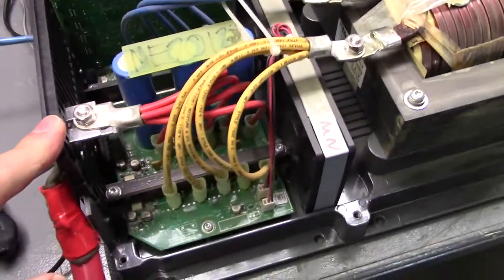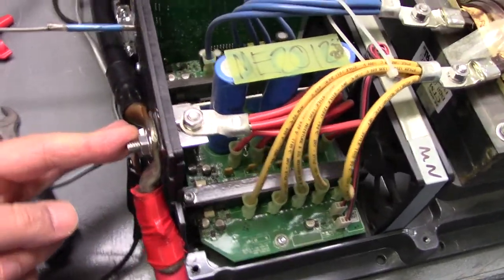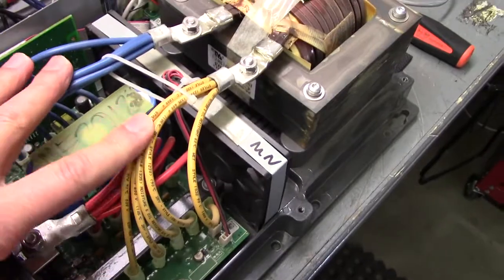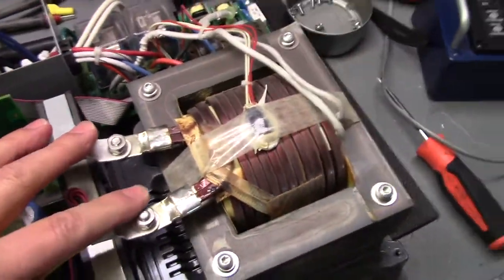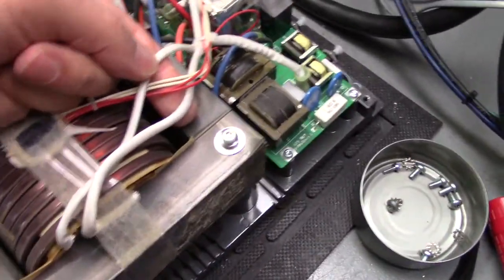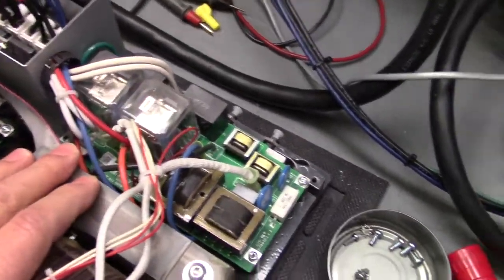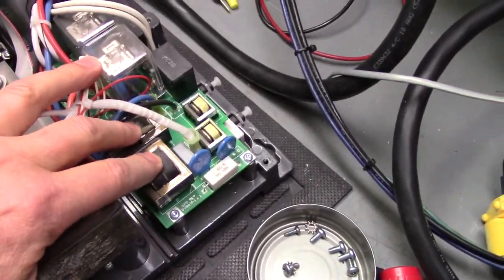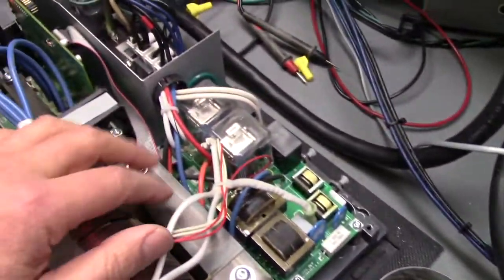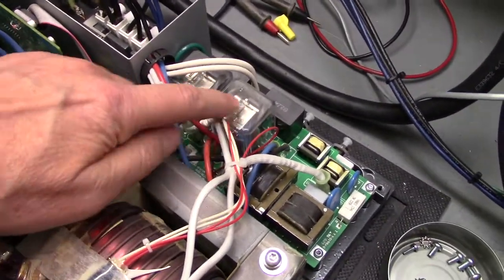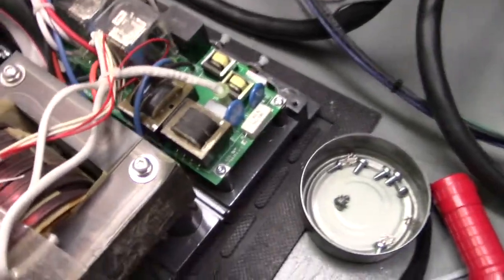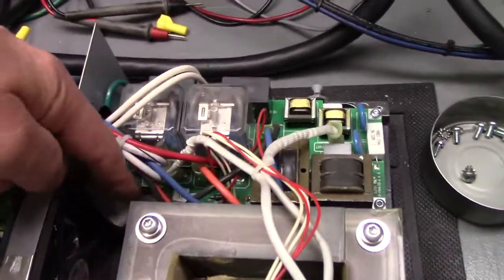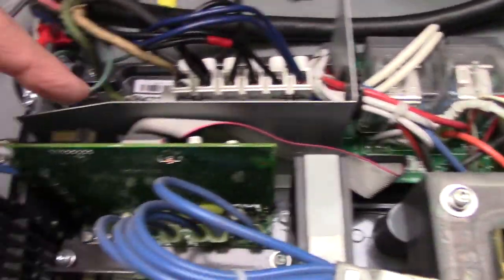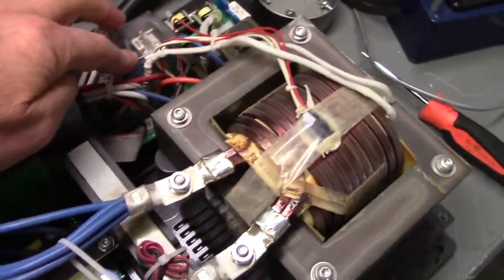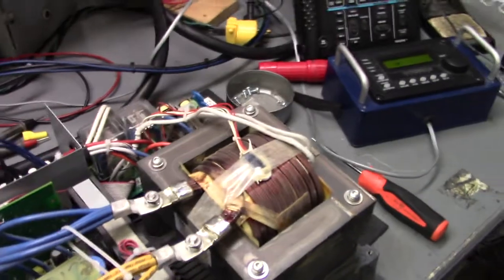The DC battery voltage coming into the inverter gets switched back and forth into the primary of the transformer, and the output of the transformer goes, with two wires, into what we call the AC board. The AC board has feedback sense transformers for voltage and current, and it has a ground bond relay and a power transfer relay. There is also some filtering. You have a cable coming from the AC board back to the control board, so the control board can operate the relays and read the sense transformers. So that's the inside.